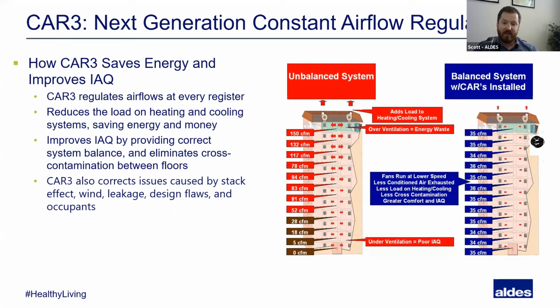So by correcting all of this, and like I said, we have case studies that show that by just having the airflow that you need, and not more and not less, you can save a tremendous amount on your utilities. We've seen 27% savings on the utility costs for an entire building just by installing the airflow regulator. So very, very short ROI. In that case, it was like 9 months. So it's kind of a no-brainer.